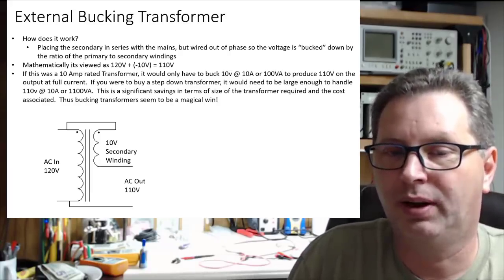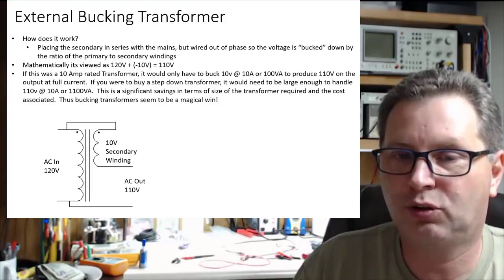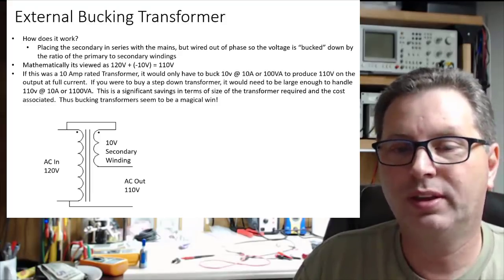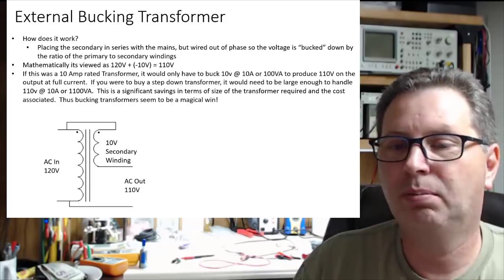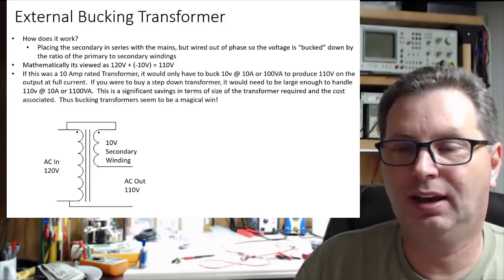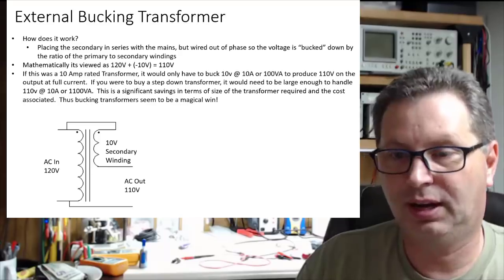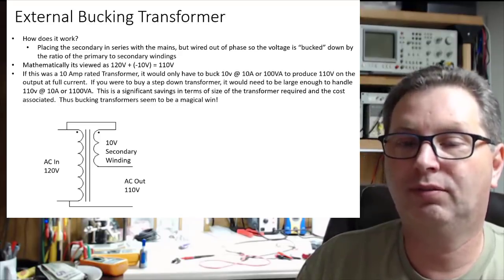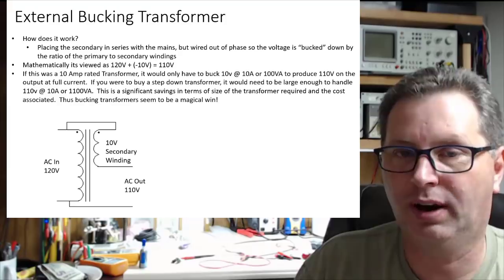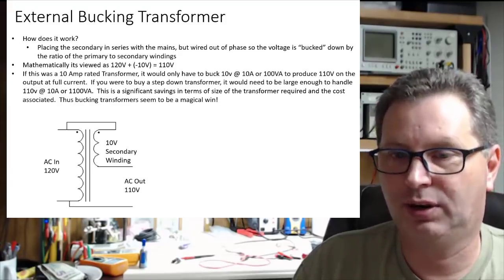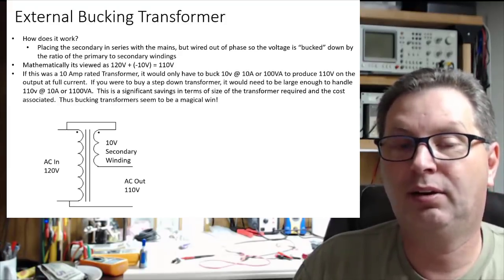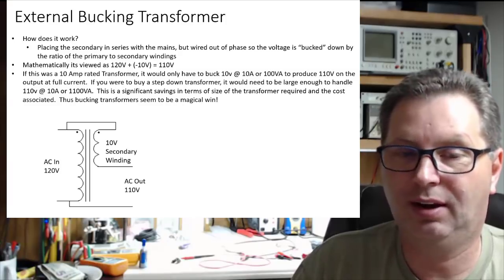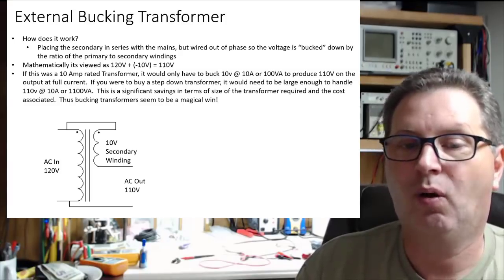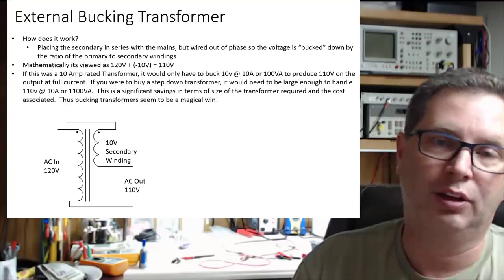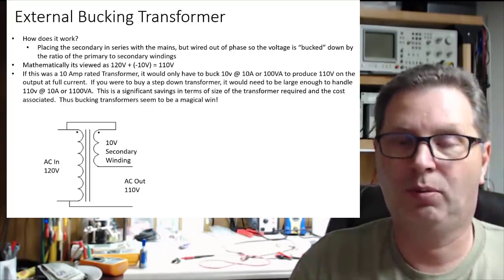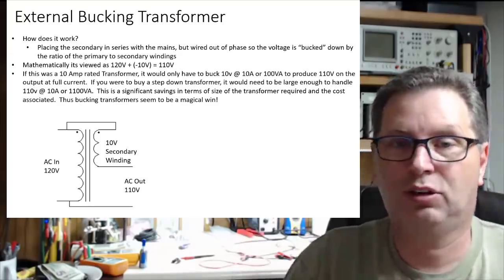Here's an example. If this was a 10 amp rated transformer for the secondary, it would only need to buck 10 volts at 10 amps, or 100 volt-amps, to produce 110 volts on the output at full current. If you instead bought a step-down transformer, it would need to handle 110 volts on the secondary at 10 amps, making it a 1,100 volt-amp transformer—in other words, a much, much larger transformer.